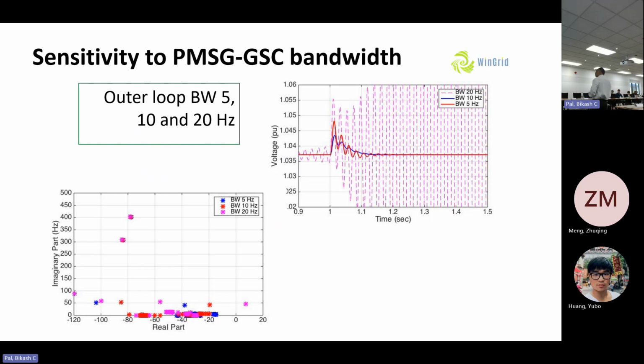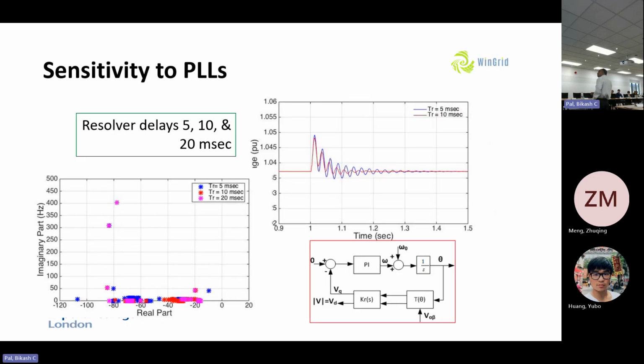So this is the outer loop, and then the speed of the PLL. The PLL response can be 5 milliseconds, and you see that with 5 milliseconds, this is now more oscillatory, whereas with 20 milliseconds, 10 milliseconds, it is less oscillatory. So this clearly says with 20 milliseconds, the eigenvalues are here, whereas with 5 milliseconds, the eigenvalues are close.